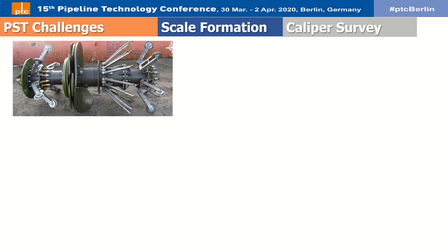The configuration for the 32-inch caliper pig used had 16 caliper arms and two odometer distance measurement wheels. The 16 caliper arms activated eight caliper sensors — two arms per sensor. The aim of the caliper survey was to report the location and approximate quantity of calcium carbonate deposits formed within the pipeline as an unwanted consequence of pH stabilization.